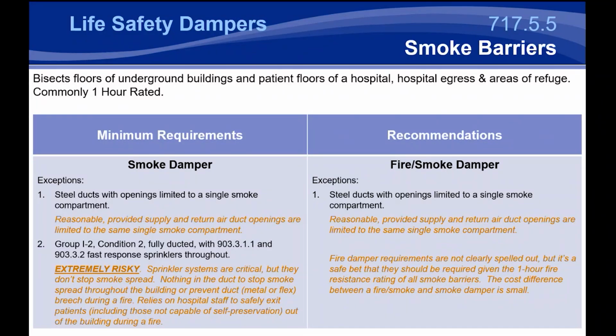Now, smoke barriers are commonly 1 hour rated. So with the smoke barrier being commonly 1 hour rated, a lot of times they're fire partitions as well. So they have similar requirements, and they have to maintain the requirements of both. So there's a fire rating that requires a fire smoke damper, and there's a smoke rating as well. Now, there are a couple of exceptions for removing the smoke damper in these smoke barriers.